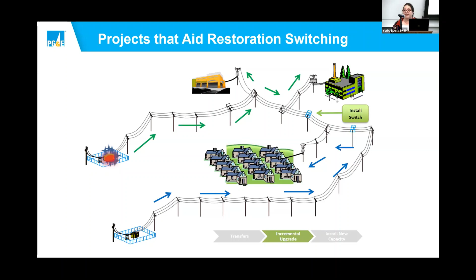Just a little bit about how the power grid works, the restoration switching. There's a substation, two substations on the left. You can think of the high one and the low one. The high one has a failure. That subdivision, that set of many houses, can be moved from one circuit to another based on switches that are in the field. So that's often how we restore in an outage, is to move sets of customers based on the switches that exist in the field. And if we can install new ones to help that process, we'll do so.